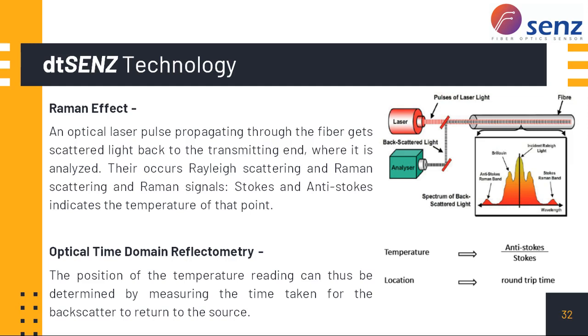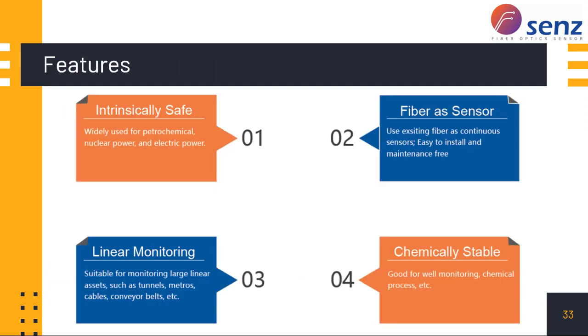And based on the time domain, like how much time it takes to reflect back, we can ascertain that this temperature signal is coming from what portion of the fiber. At every 1 meter, we can find out what is the temperature with a reasonable accuracy, depending on the laser source and the kind of analyzer. So we can do even 10 kilometers or 20 kilometers of temperature sensing. Intrinsically safe, chemically stable, it is a linear monitoring.